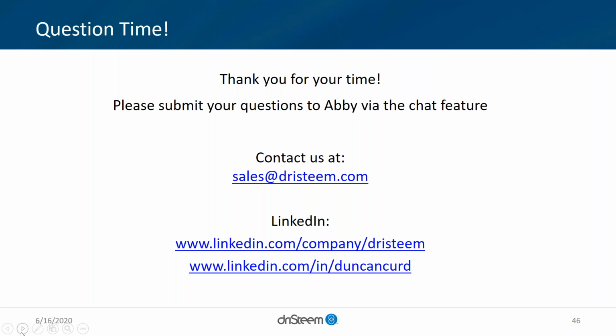A very good question, and actually a fairly critical one. There's some pretty good research dating back some time as to the potential downside of utilizing direct injection, or steam directly injected into the duct or air handling unit. The reason is that boiler steam may be dangerous to human occupants, since a number of chemicals, such as amines and other compounds, may be present in boiler steam to avoid scaling. For this reason, if you'd like to use boiler steam as an energy source, we recommend a steam-to-steam unit.